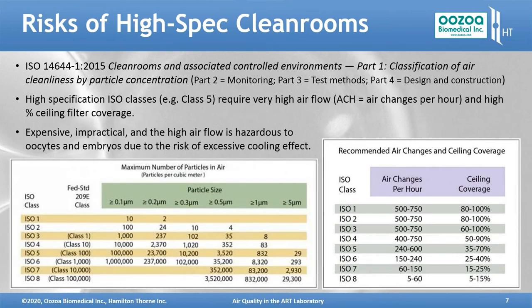If you go for one of these really very high spec clean rooms, there are some risks. I mentioned the ISO standard before, the ISO 14644 part one, last reviewed 2015, which means it's probably under review again right now. It's about clean rooms and associated controlled environments. And part one is about classification of air cleanliness by particle concentration. The three other parts are that same ISO standard, but part one is what affects us right now. You need to know that high specification ISO classes like class 5 require very high airflow in terms of air changes per hour, which is usually abbreviated as ACH, and a high percentage ceiling filter coverage.